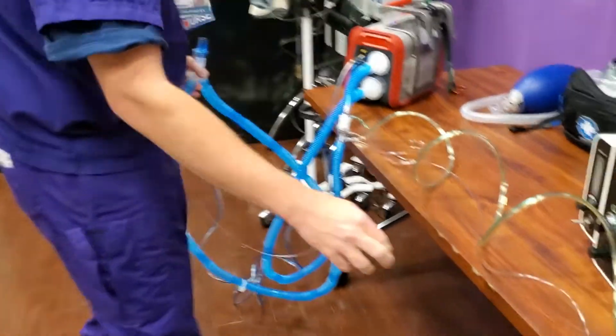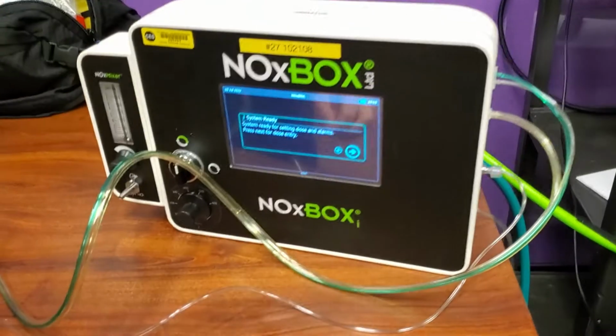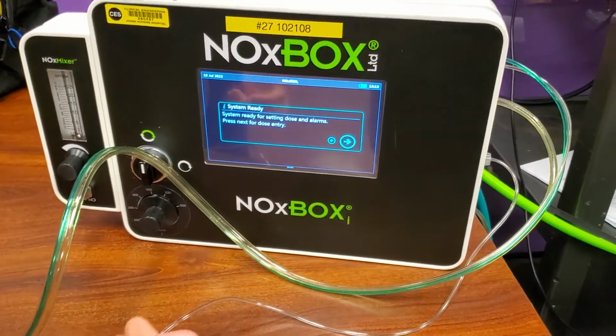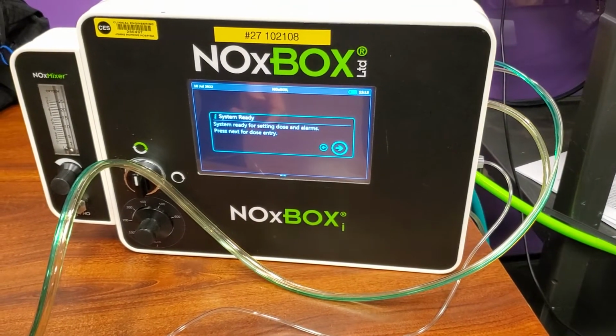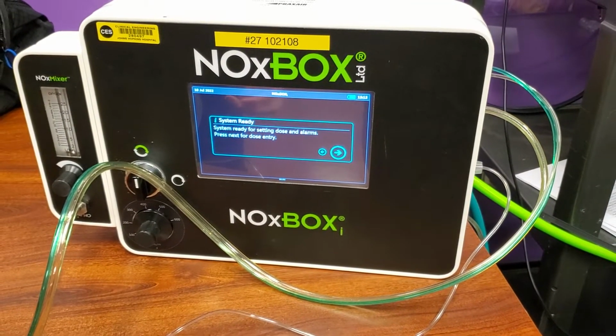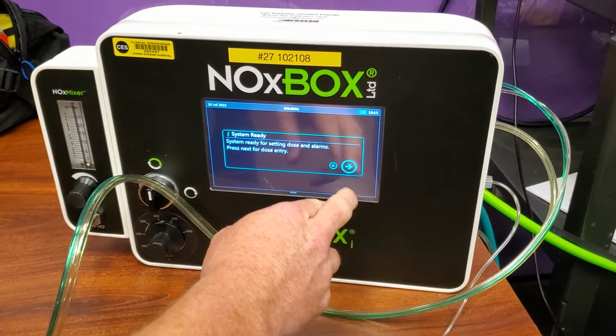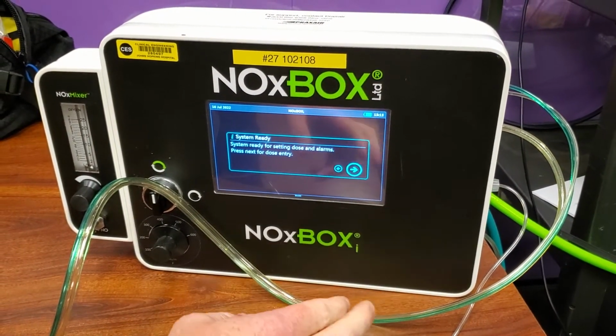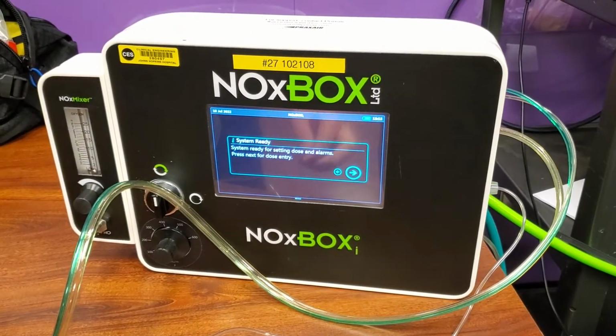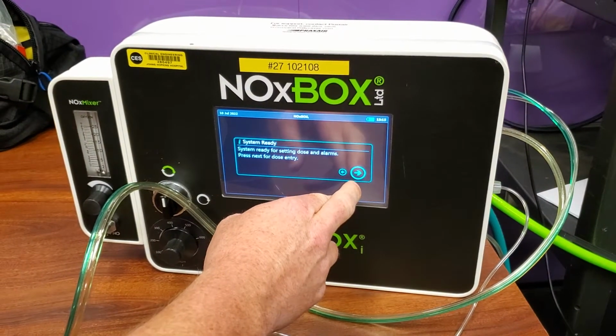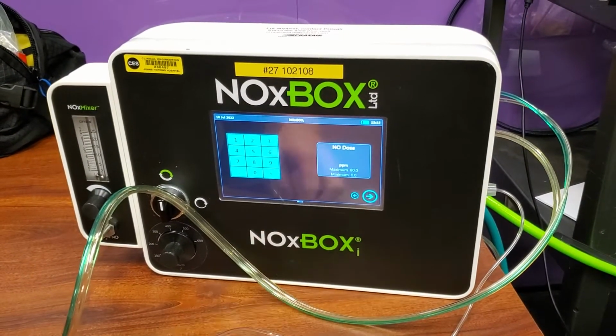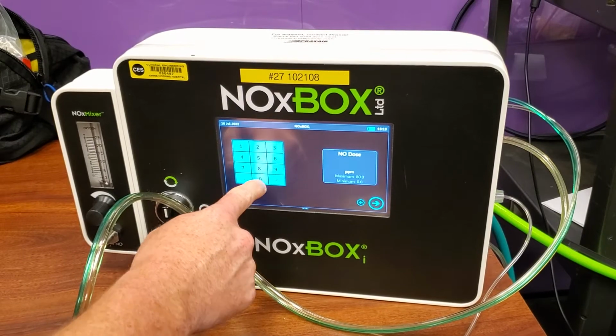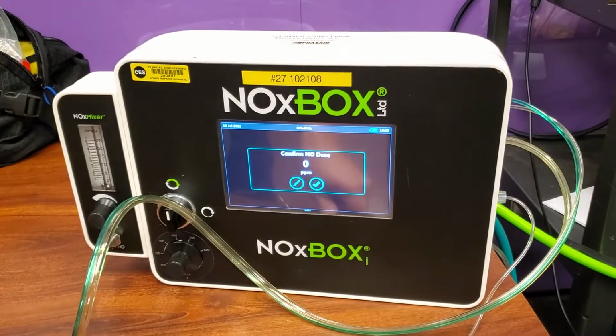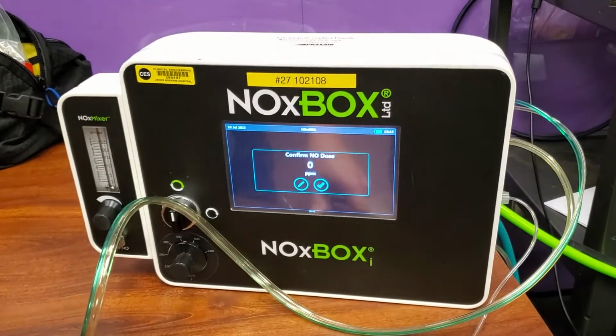Okay, so we're going to go on to our next page here. Now the system's ready for us to set. We can place a dose in. If you were completely ready just to hook it up to the patient and get going, you could set your dose there. But for purposes here, I'll just show you how you would put it in a standby mode while you're finishing getting the patient set up and not switching them over to the ventilator quite yet. So we're going to set our original NO dose to 0. Good there. We're going to confirm that dose is 0.